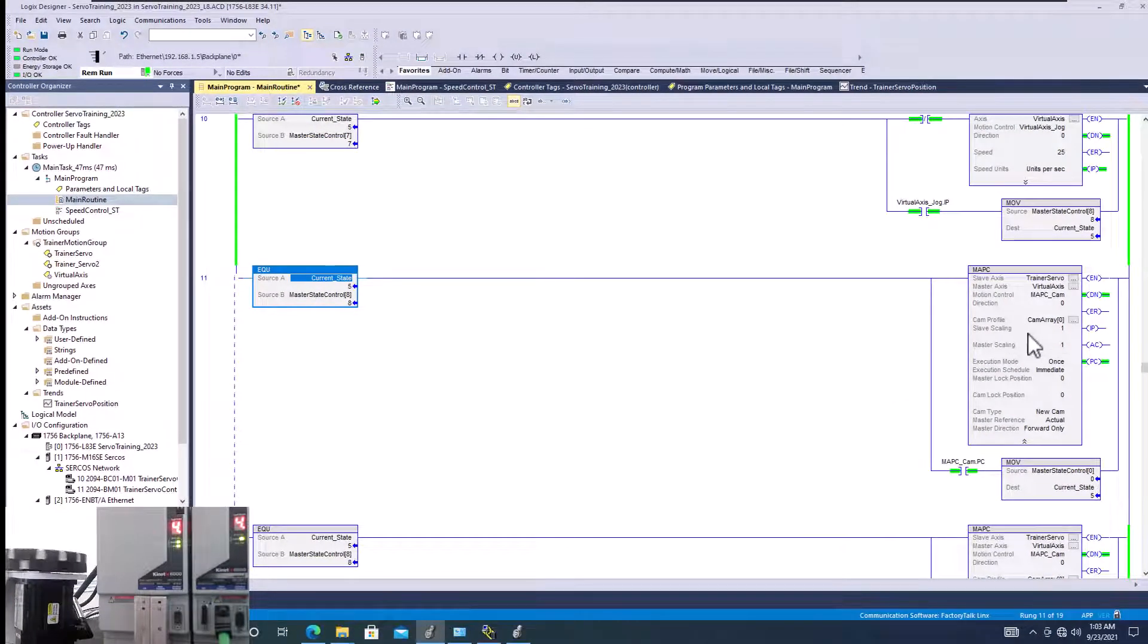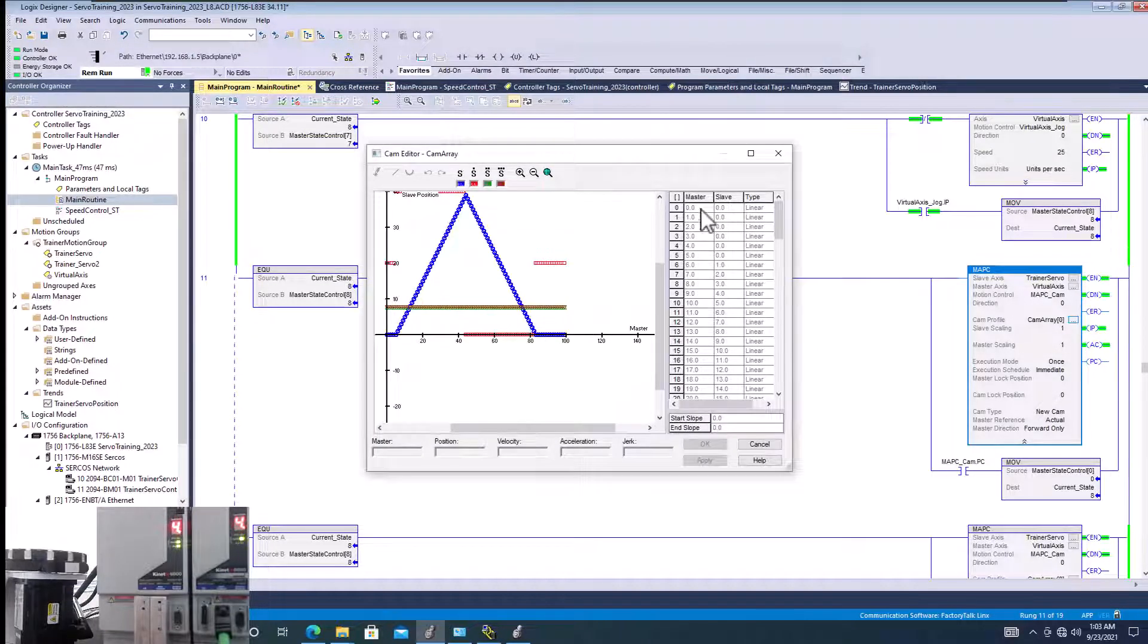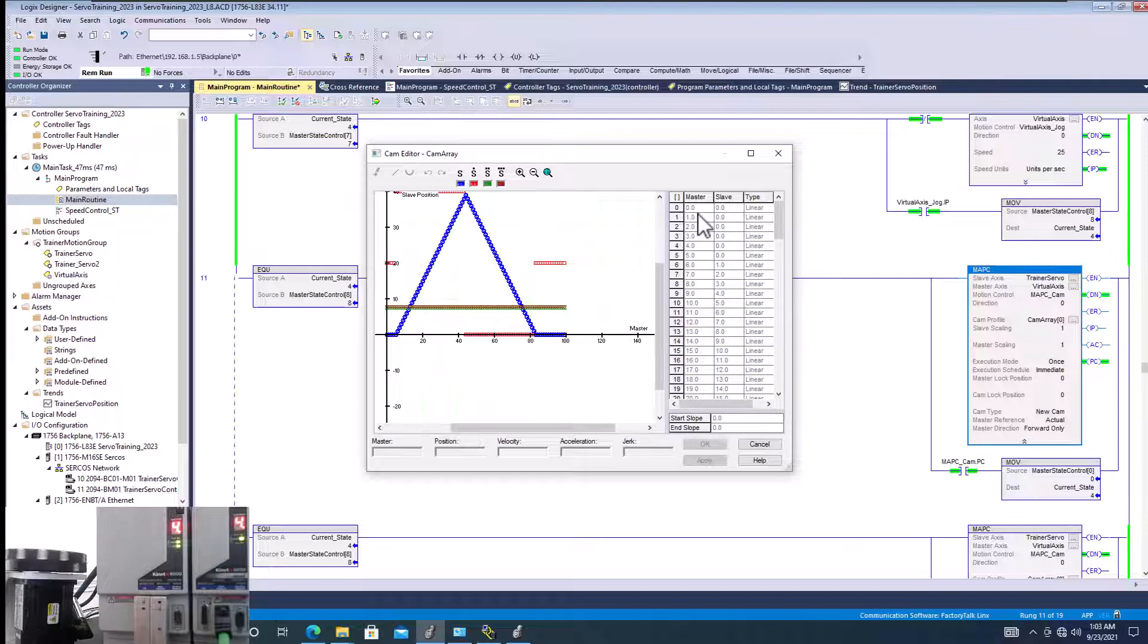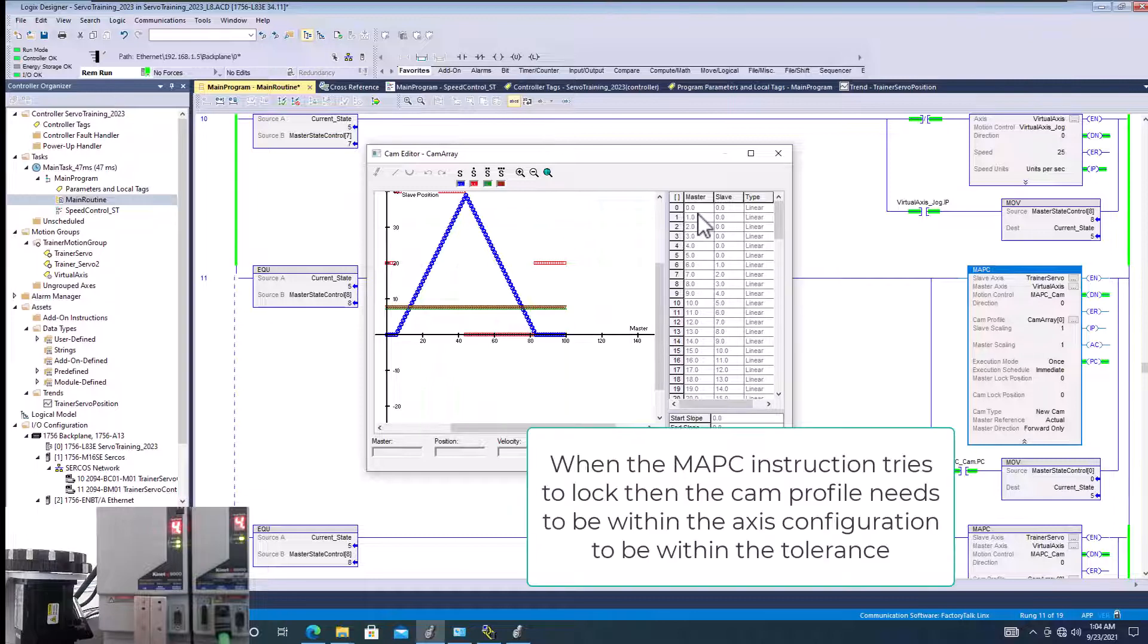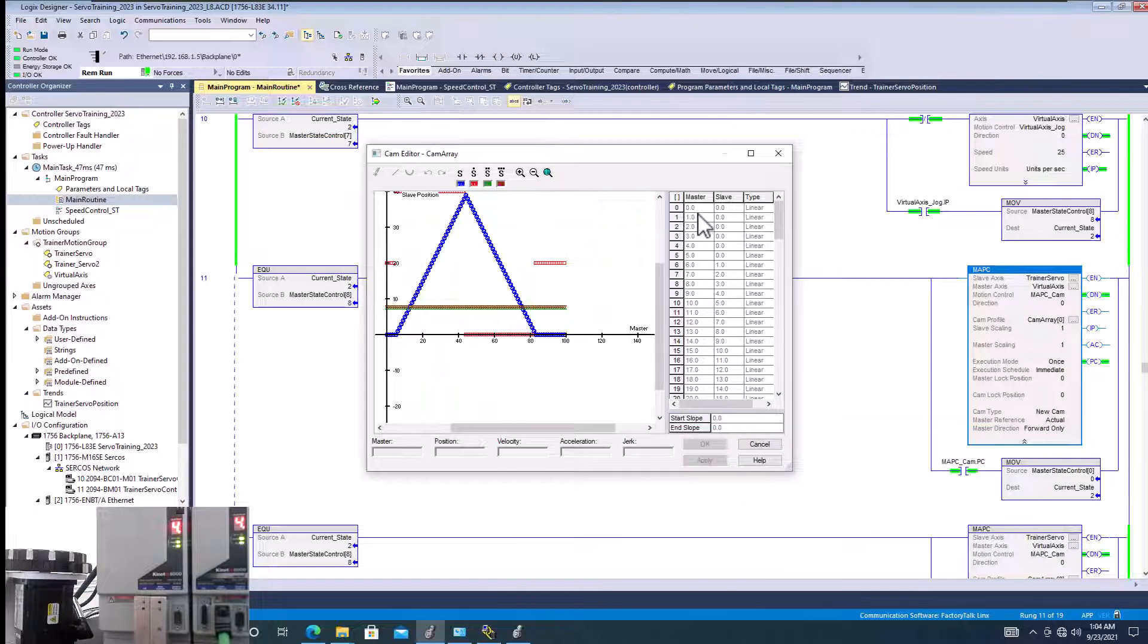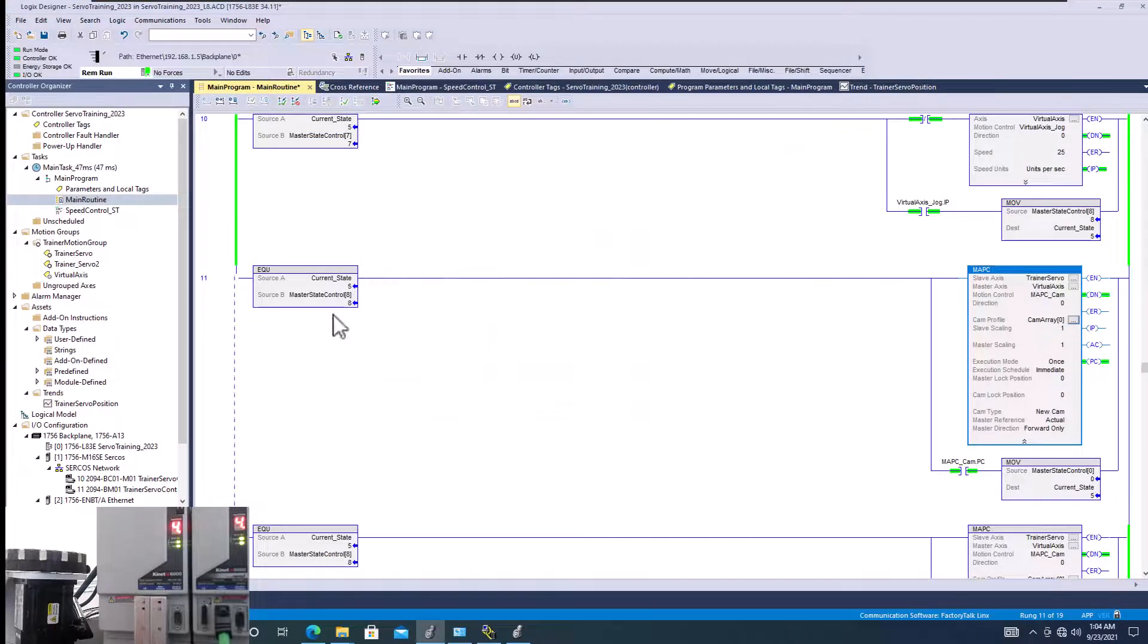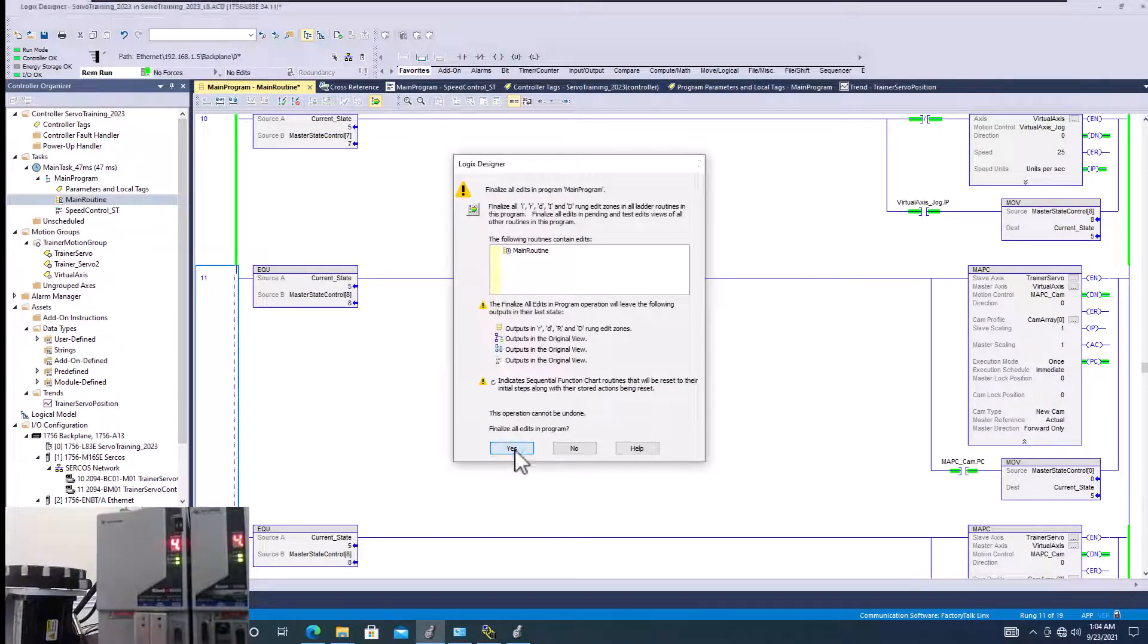Now if you're getting this error, I want to talk about that a little bit closer, because in this position right here, your master where you're starting, 90% of stuff does start at zero. However, you can start not from zero. But keep in mind that when the MAPC instruction has an error of 13 and an extended error of 10, basically what that's saying is your cam lock position is out of range. So where you're trying to lock your cam in, it's out of range from what it can be. And so how do you fix that?